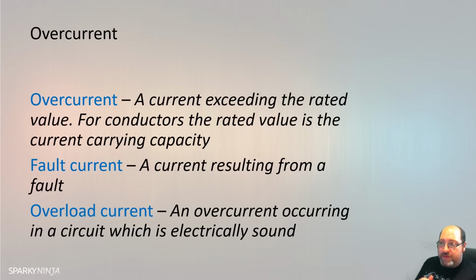Now, an overload current, like the example I just gave, is an overcurrent that occurs in a circuit which is electrically sound. So there is no fault present on the circuit. A circuit that can carry an overload current but not actually contain a fault: two common types are a motor doing too much work, or, most common, a socket outlet circuit where we have too many things plugged into the circuit. A shower circuit or a cooker circuit can't overload because they are fixed ratings. They are 10 kilowatt, 6 kilowatt, 3.5 kilowatt, whatever they are. They won't pull more in a fault-free scenario.